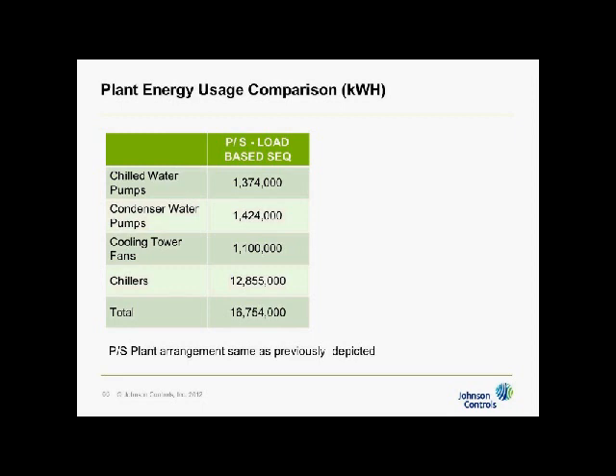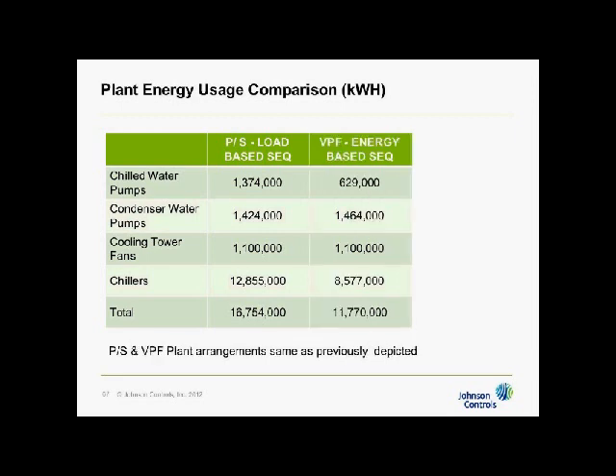A total for that year was almost 16.8 million kilowatt hours. And again, that was based on the three 2,000-ton chillers. Next, we looked at the VPF plant, energy-based sequencing. You can see the immediate savings in the chill water pumps were now around 629,000 kilowatt hours annually versus the 1.4 from before. The condenser water pumps are roughly the same, with a slight difference in loadings when we use energy-based sequencing.